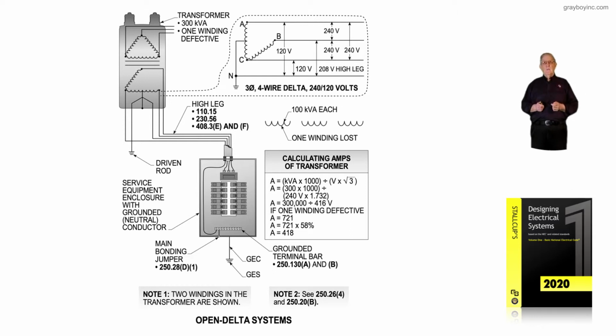Now, reviewing the illustration, let's look at say the A phase. Do we get 120 volts to ground? Yes, we do. Look at the C phase. Do we get 120 volts to ground? Yes, you do. But phase to phase, we get 240 volts. But now, once again, when we review B, notice we are going through that 240 volt winding and the 120 volt winding to ground.